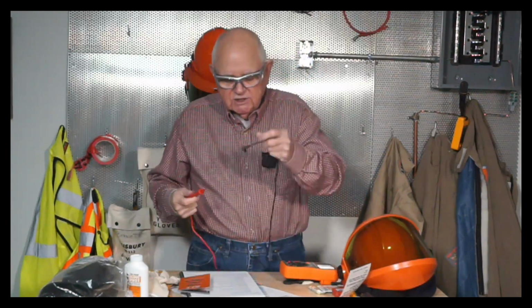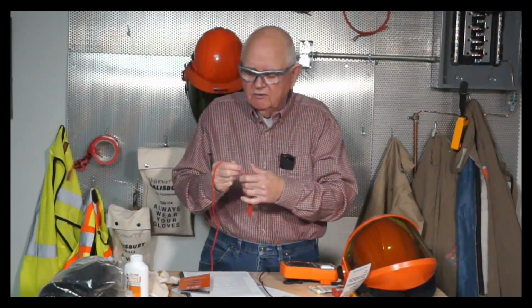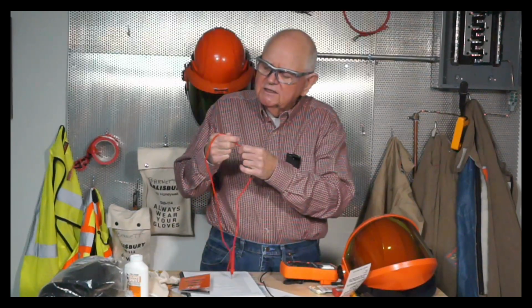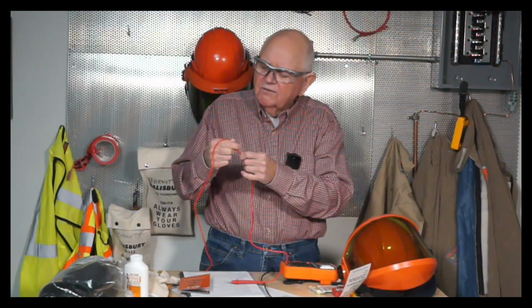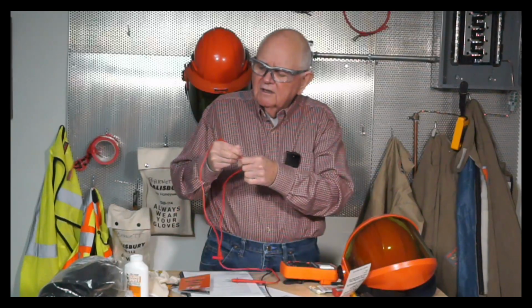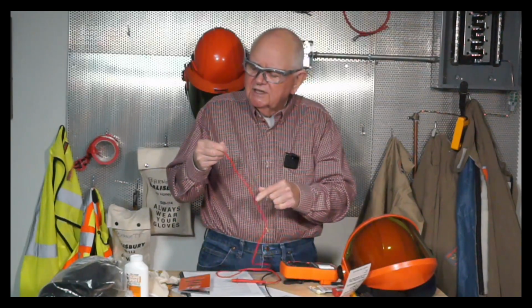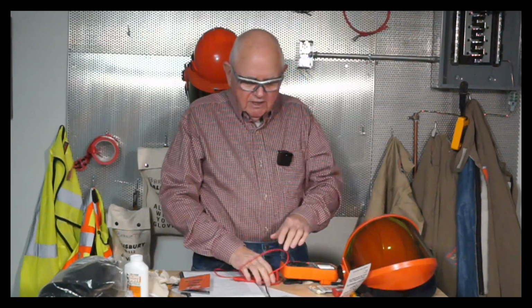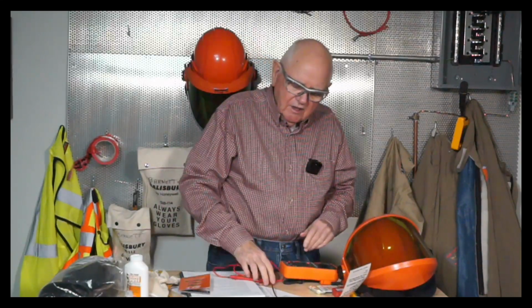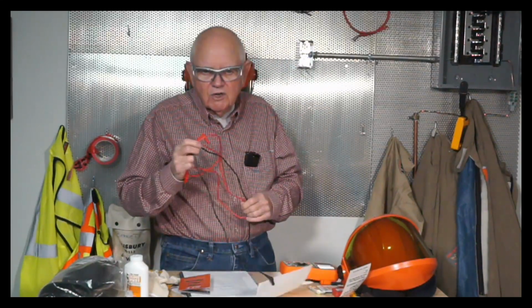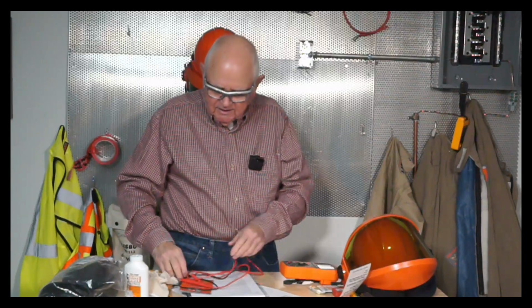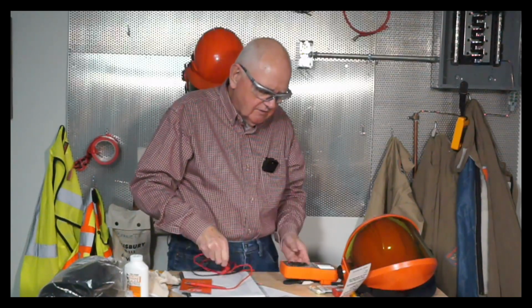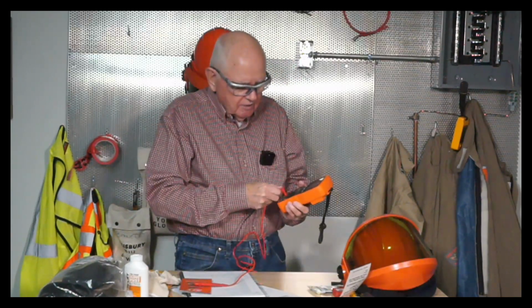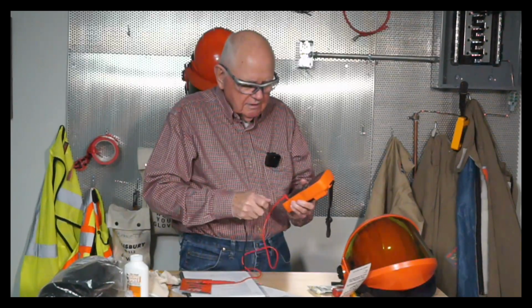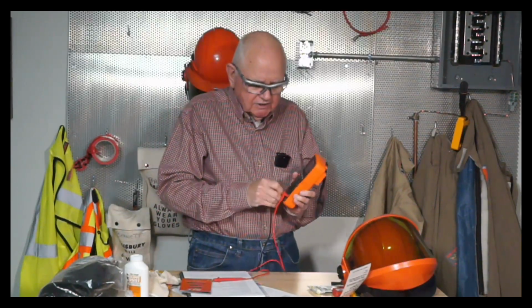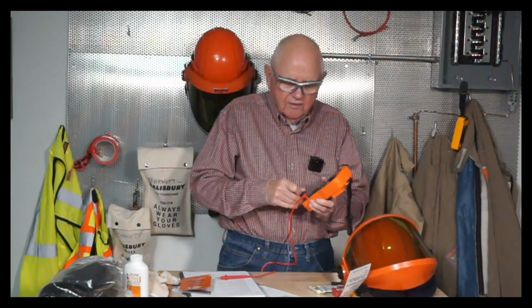And then the way I like to check my test leads, I just run my finger as I take a look at it and inspect it. In between my fingers, if there's anything wrong, I should feel it. And I don't repair test leads. I just cut them in half and throw them away. Okay? So I check my meter and my test leads. One thing that I want to do, especially if I create an electrically safe work condition, if I'm doing lockout tagout, is set my meter up as I'm going to use it in the field to read voltage. And then I want to make sure that it works on voltage.